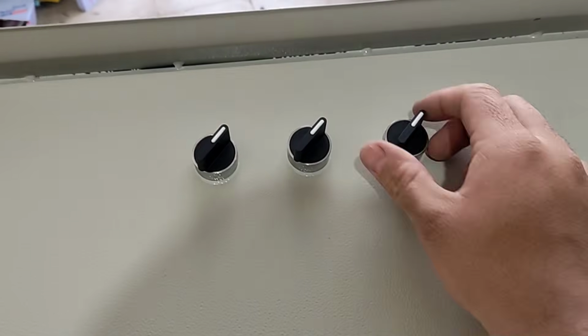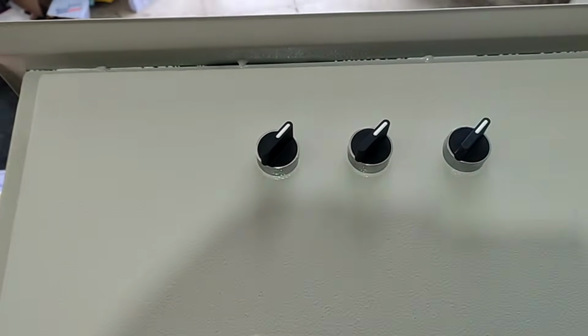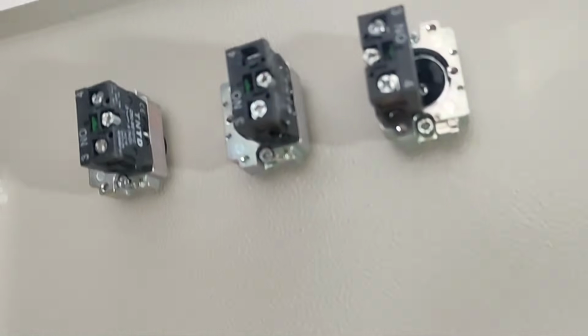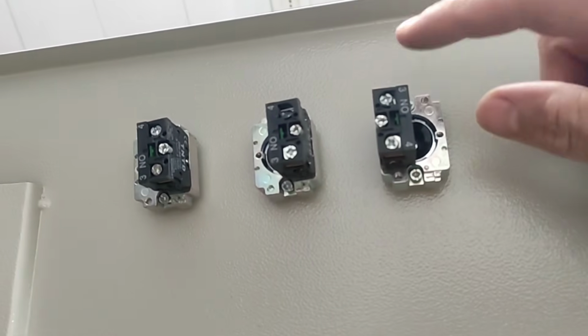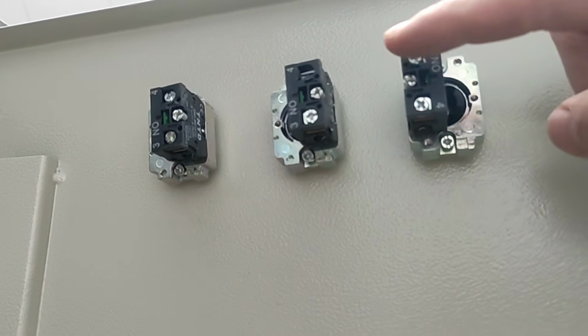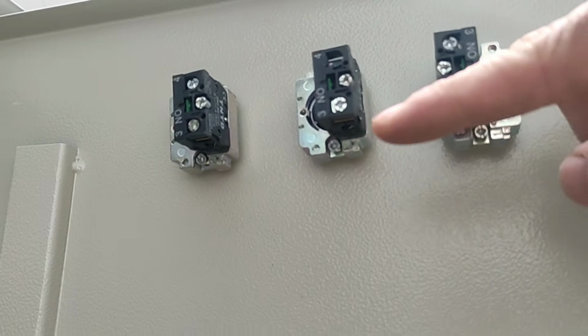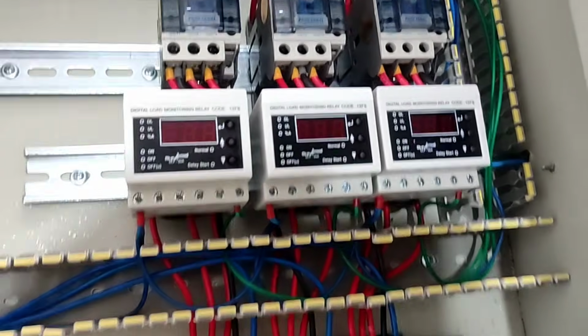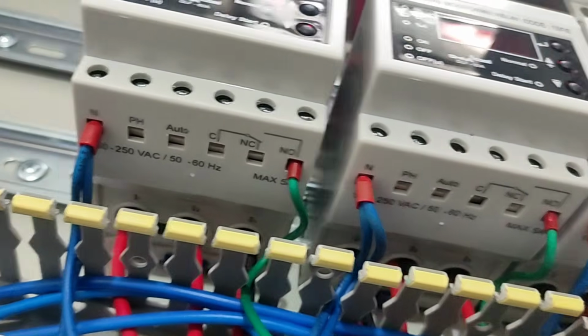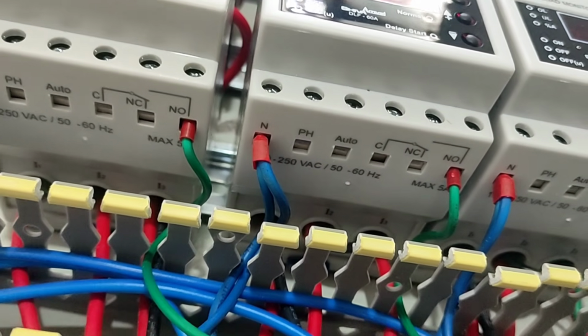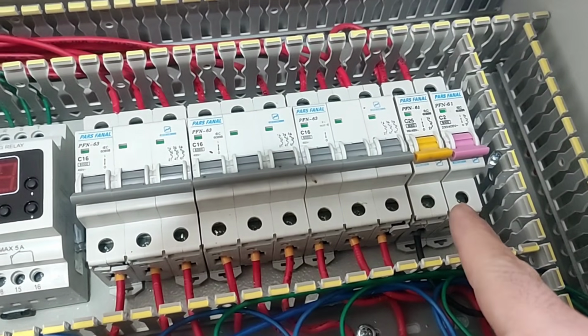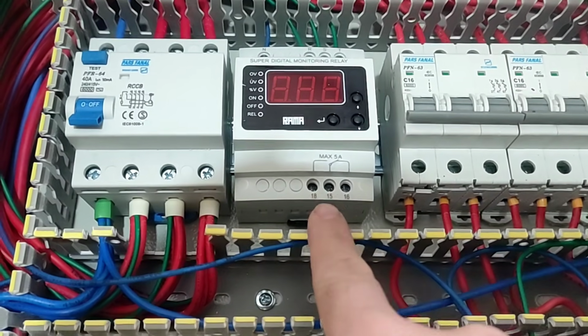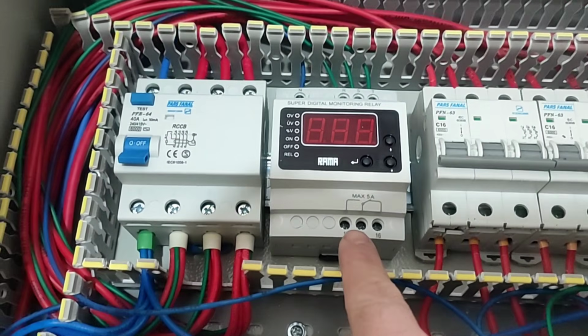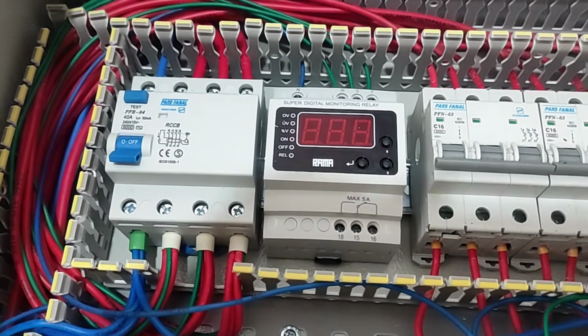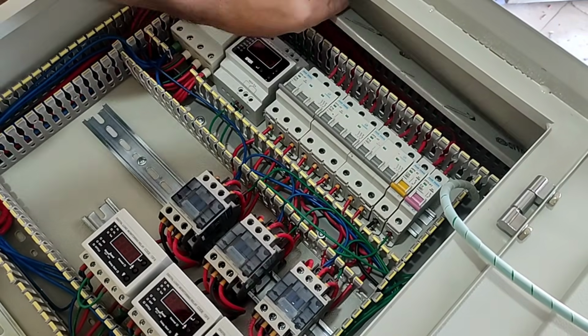To turn on the electric motors, we use 3 selector switches on the door of the electrical panel. The input power of these switches is connected to the output of the phase controller relay, and their output is connected to the input part of the current controller relay. To complete the command circuit, we connect a phase wire from the output of this switch to the input of the phase controller relay, and we connect its output to the input of the selector switches. The electrical panel wiring is finished.